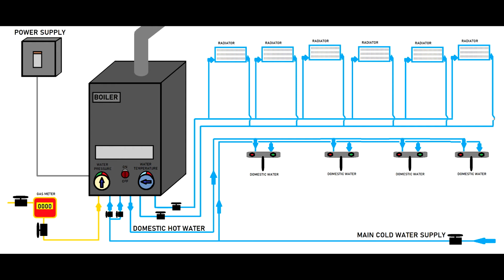A professional gas registered engineer will install the gas to the boiler and will commission the boiler so accidents will not happen. As you'll see now, we enable the gas meter and the engineer will give you a commissioning certificate and a safety certificate that complies with the regulations. Now we turn the boiler on for the first time, so the boiler will have a health check. You will check all the parameters, if all the sensors are okay, if the water pressure is okay. Actually, the boiler has a printed circuit board and the software allows the boiler to do an electronic self-check to see if every item that must send signals to the PC board is healthy.